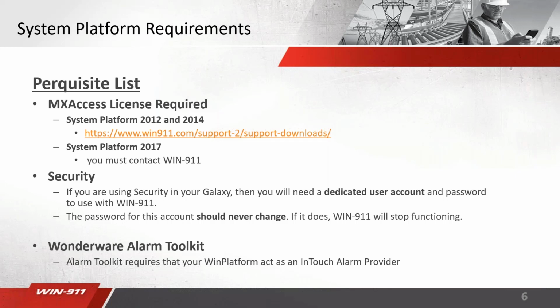Another thing to be aware of here is security. If you are using security in your Galaxy, you will need a dedicated user account and password to use for WIN-911. The password for that account should never change. If it does, WIN-911 will stop functioning.